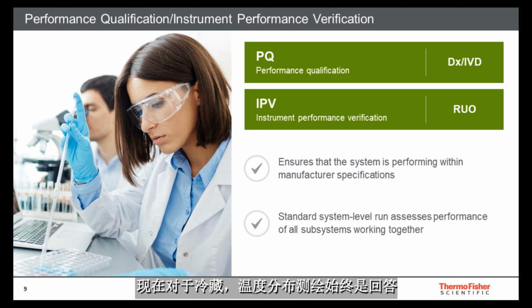And now for cold storage, temperature mapping is always the best test method to answer the many PQ questions required by the customer. Testing with the unit with a simulated load, open door to simulate sample pulls, power off testing for possible future power failures, and different shelf configuration testing are some of the common tests that are included in the PQ. If the unit can be used at different temperatures, testing at each possible set point will also be needed.